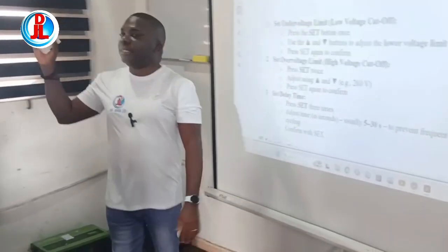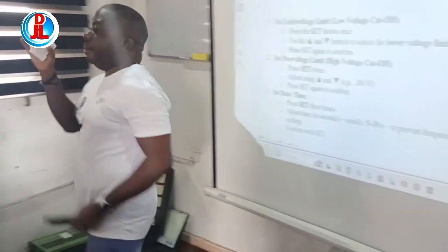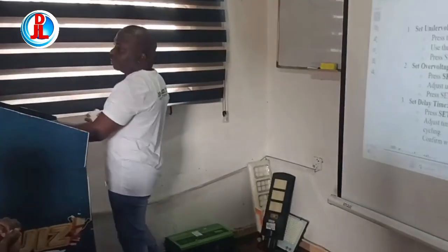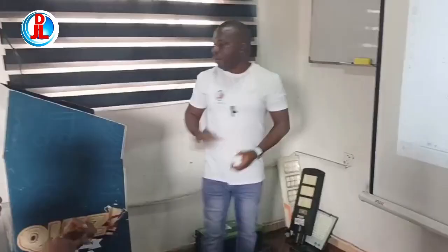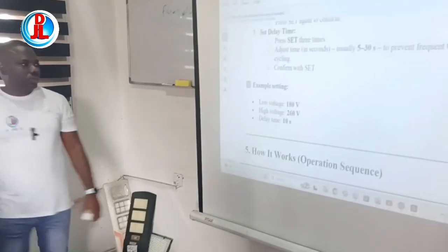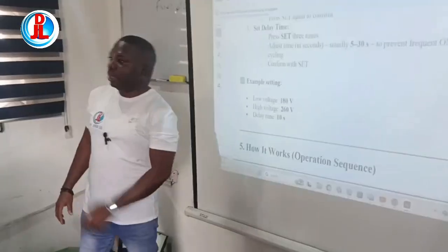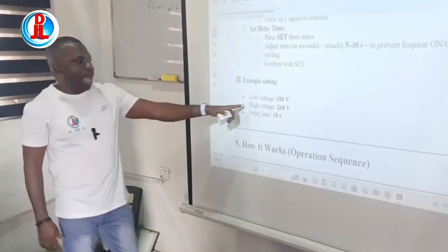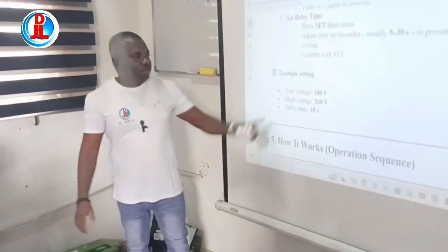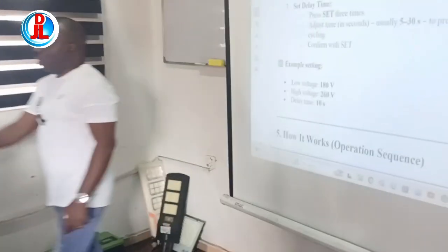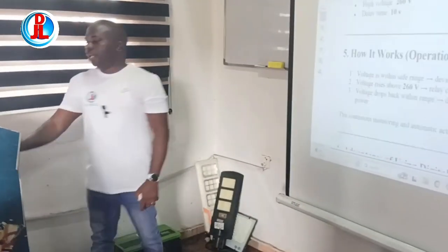Then you confirm anything you set, always confirm by pressing set again. It will now confirm, then we go to the next one. Example: low voltage 120, 180, high voltage 260, maybe delay 10 seconds, but always put ours at 30 seconds.